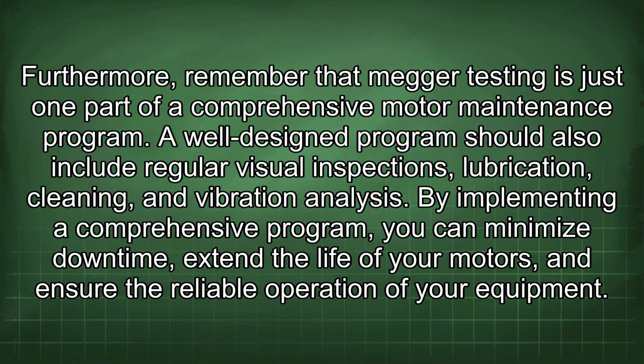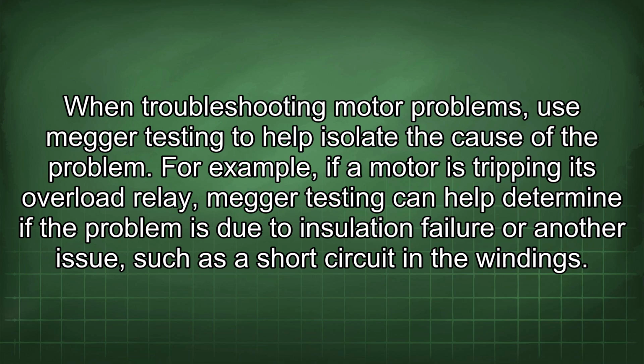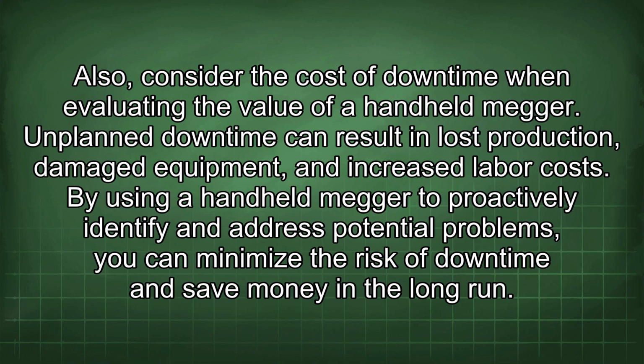of your equipment. When troubleshooting motor problems, use Megger testing to help isolate the cause of the problem. For example, if a motor is tripping its overload relay, Megger testing can help determine if the problem is due to insulation failure or another issue, such as a short circuit in the windings. Also, consider the cost of downtime when evaluating the value of a handheld Megger. Unplanned downtime can result in lost production, damaged equipment, and increased labor costs. By using a handheld Megger to proactively identify and address potential problems, you can minimize the risk of downtime and save money in the long run.